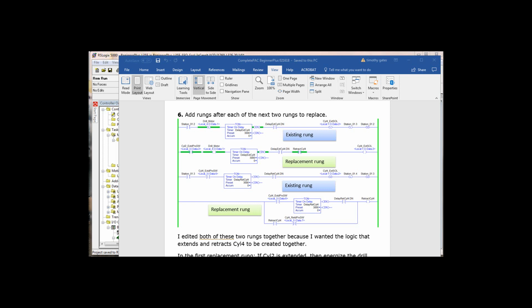Now we want to make sure that we extended cylinder 4 all the way. And for two reasons. One, we want to make sure it fully extended and not did a short drill operation because the prox on the cylinder was in the wrong position. Plus, we wanted the bit to continue to spin fully inserted in the part to remove as much debris as possible from the hole that it bored. Okay, then we unlatched cylinder 4 and we said step 4 was complete and we unlatched step 3.